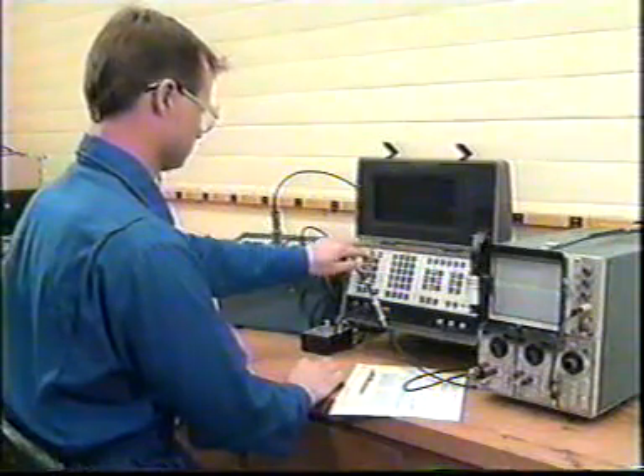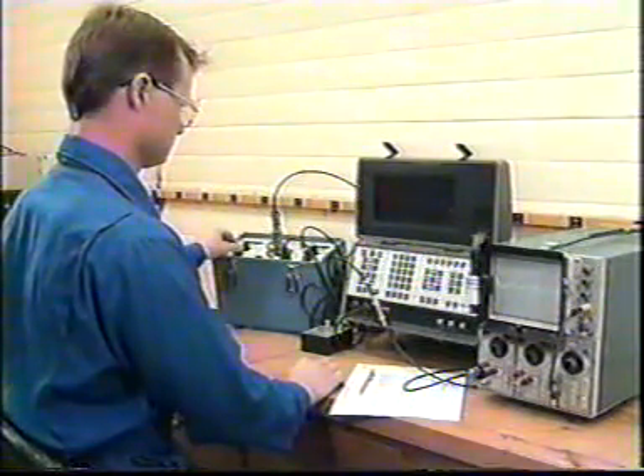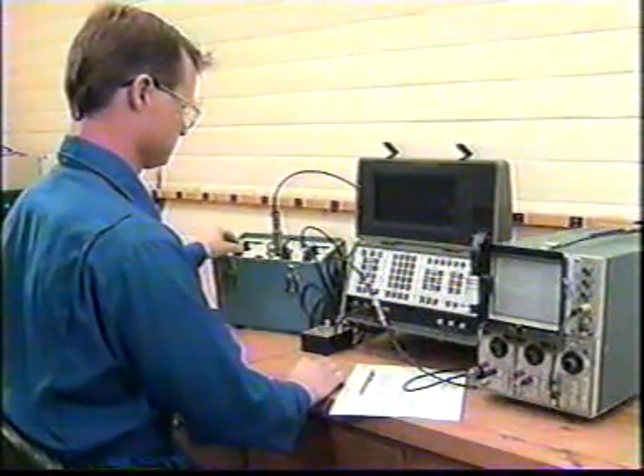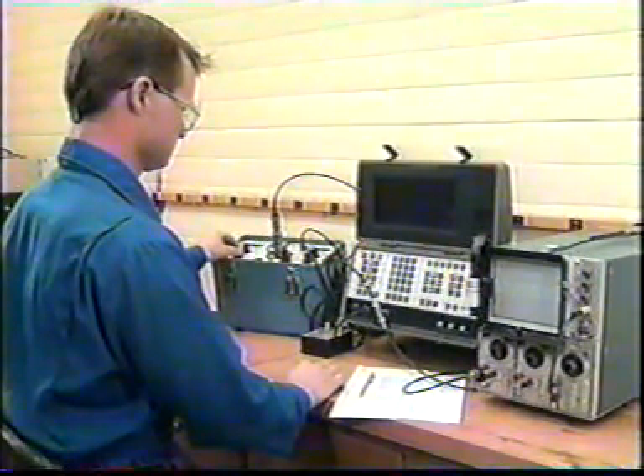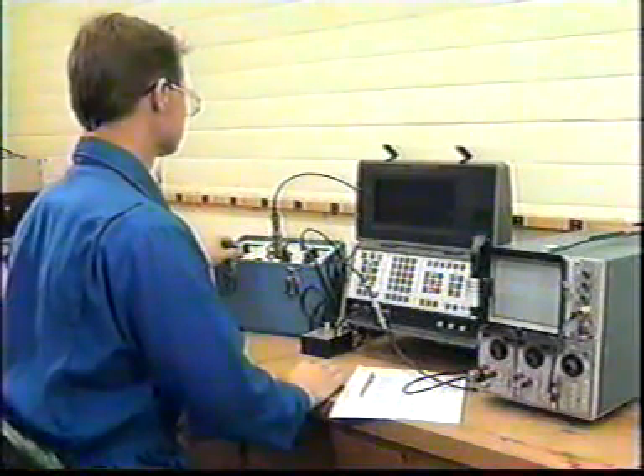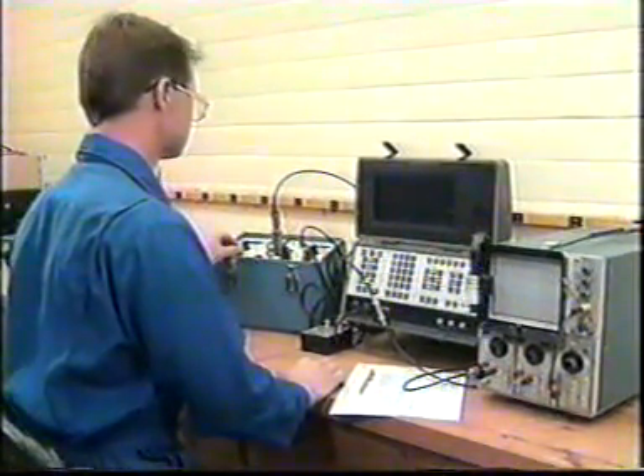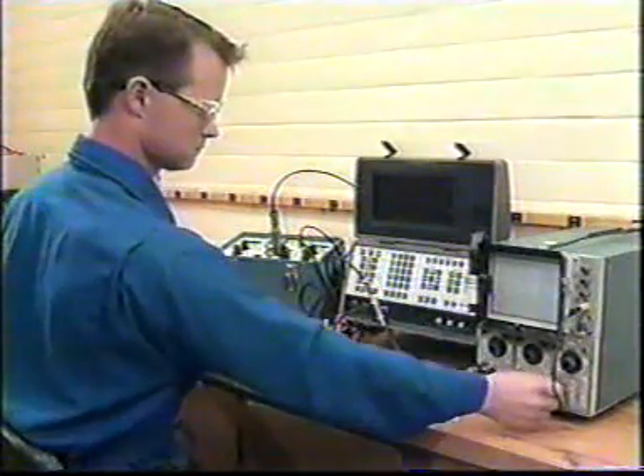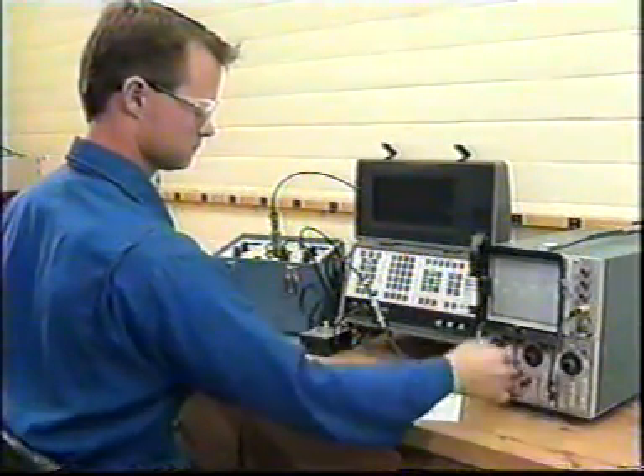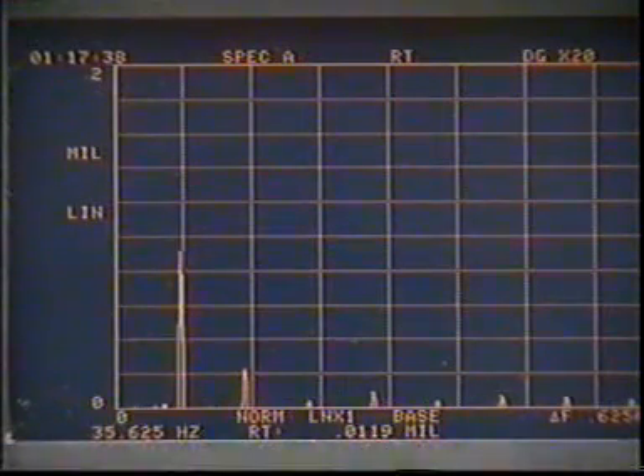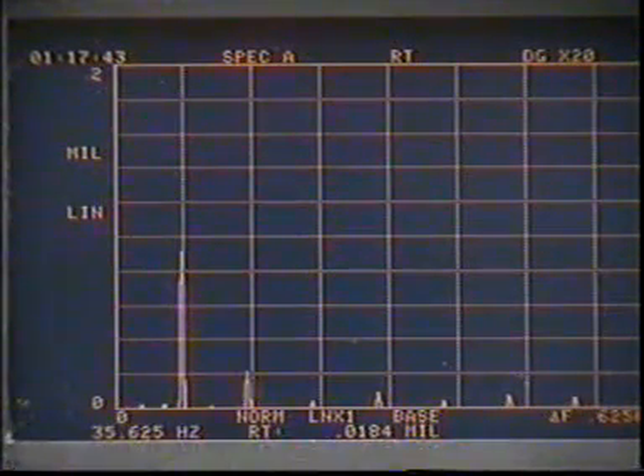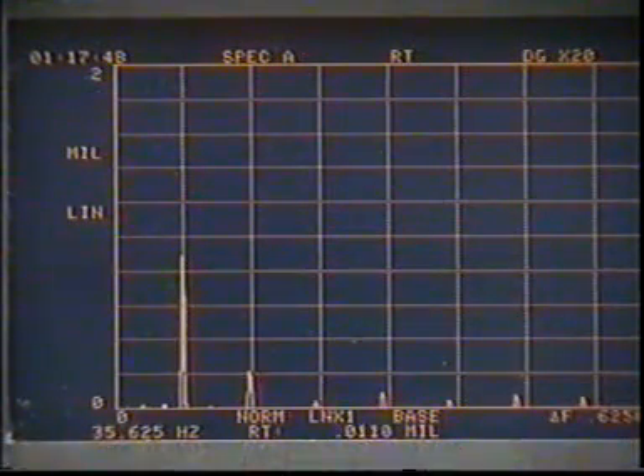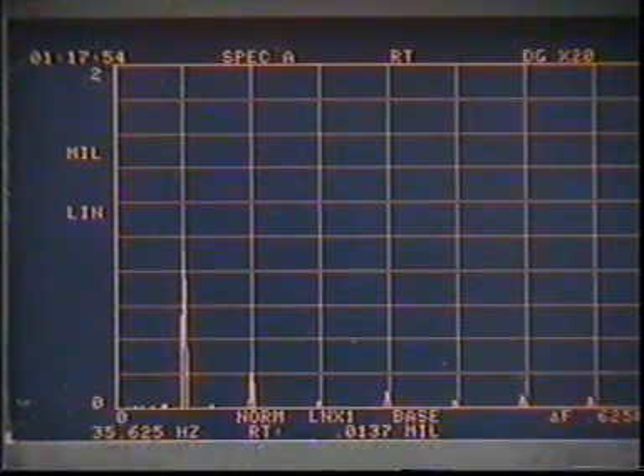Over the past several years, there have been major advances in electronics that have allowed instruments to process and plot the complex Fourier equations. The processing speed allows the output to appear as an analog signal. This process is called fast Fourier transform, or FFT. The FFT analyzer presents the signal in the frequency domain. There are several advantages for this. First, each rotating component generates a specific frequency. By plotting the amplitude versus frequency, we can correlate components to the overall vibration of the machine.